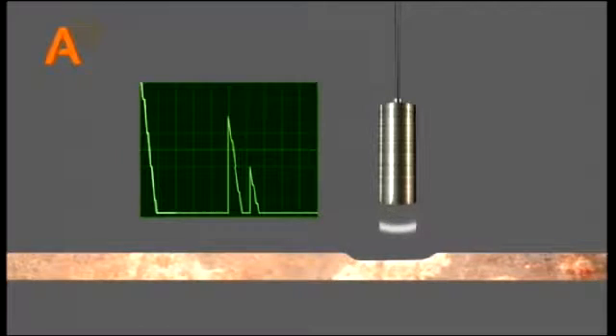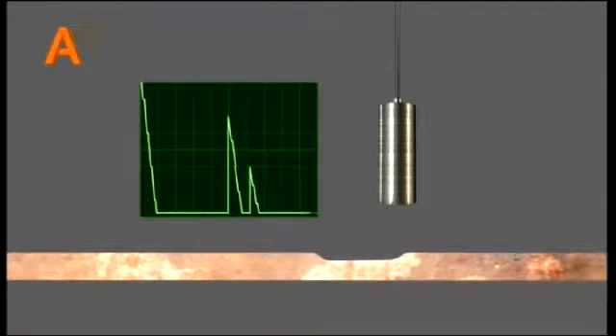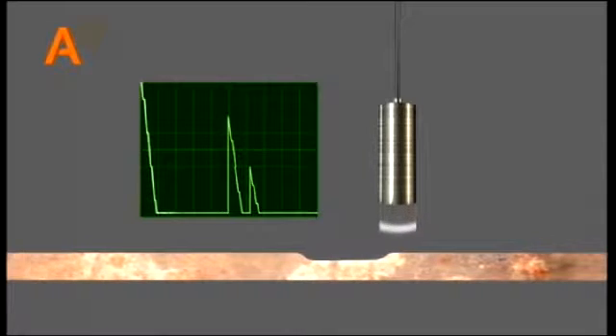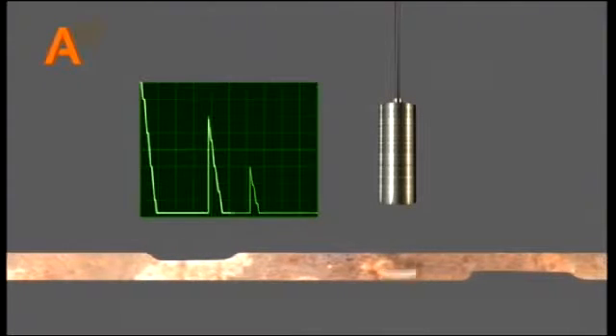results in a distance measurement between sensor and pipe wall. This provides accurate quantitative information about the internal pipe geometry, any internal corrosion and its depth.